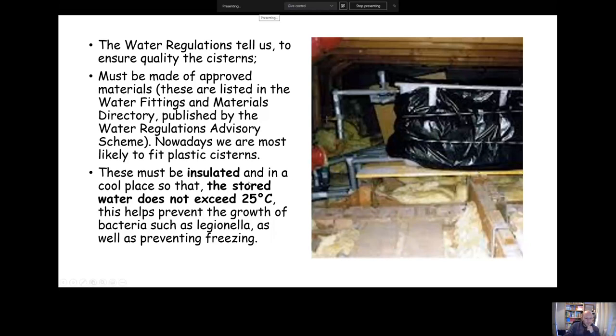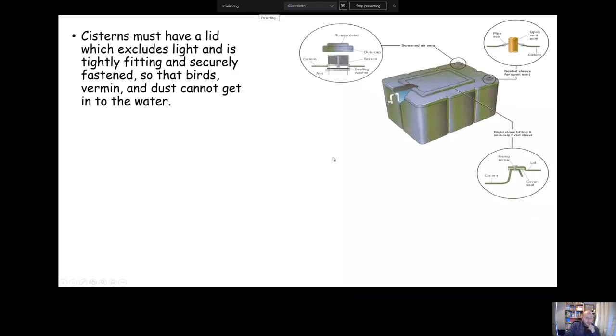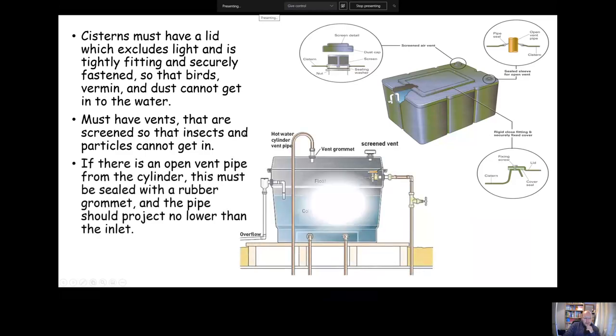As I've already said, cisterns must have a lid which will exclude light and should be tightly fitting so it stops any birds or vermin or dust getting into the cold water storage system. They must have vents, a screened air vent, to stop insects and particles getting in. If it has a vent pipe coming up from the hot water cylinder, it should be sealed with a rubber grommet to make sure it remains sealed. Another thing worth noting: when you put a vent pipe in, that shouldn't project down very far. It should literally just go into the system by maybe 25 mil and not project down any further than the inlet.